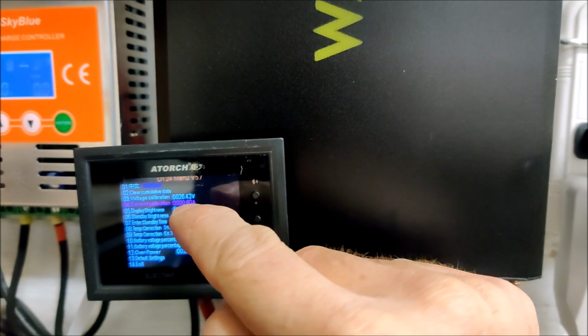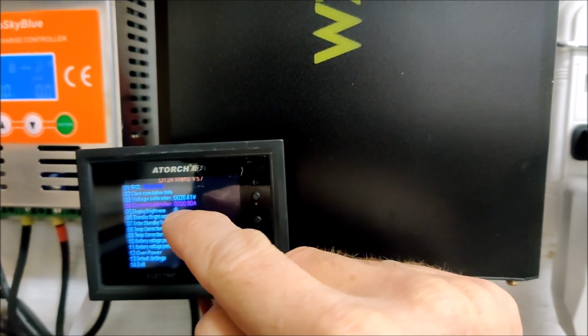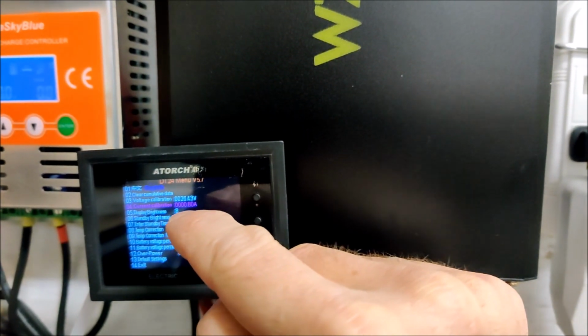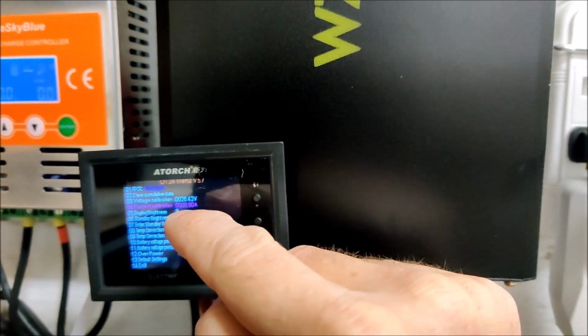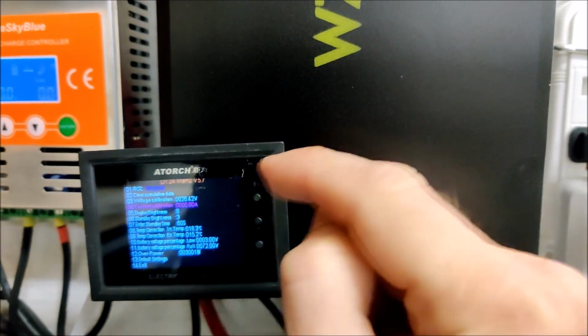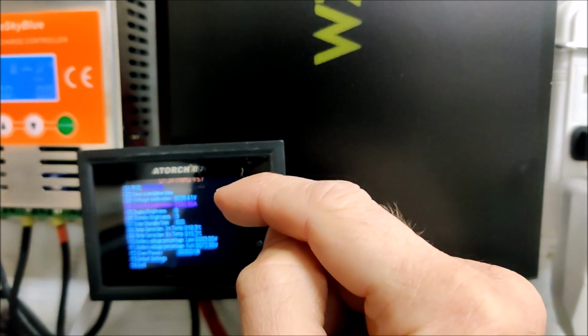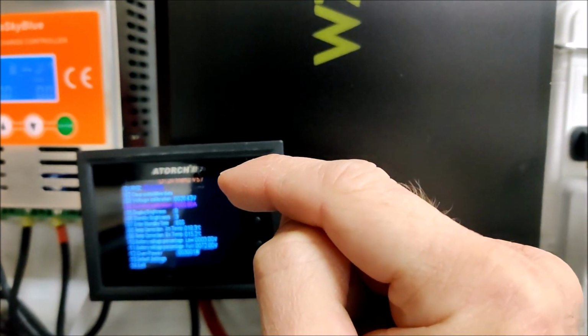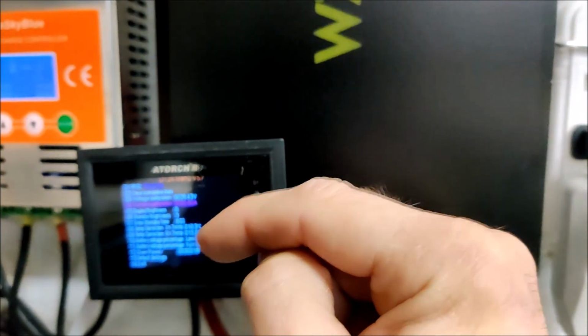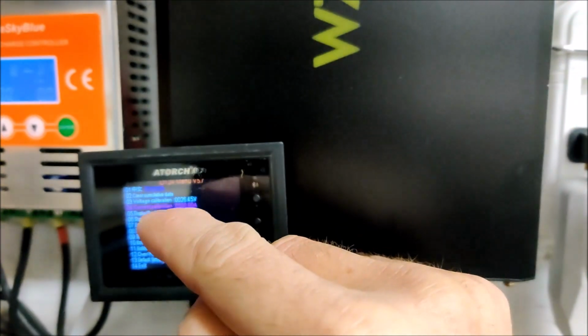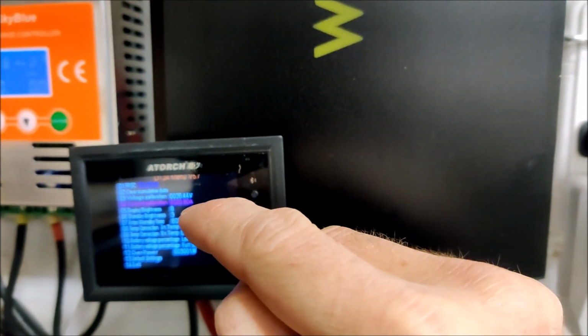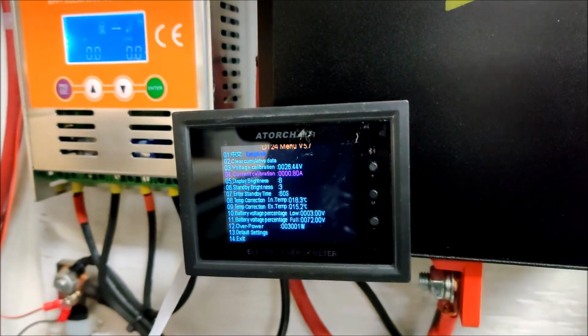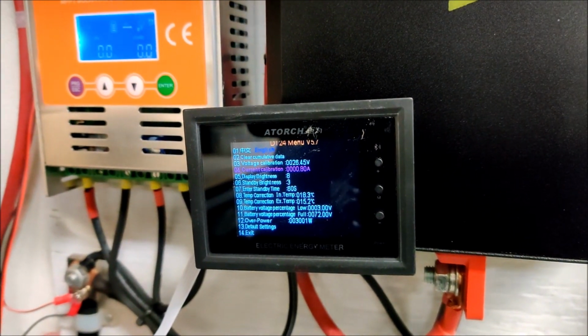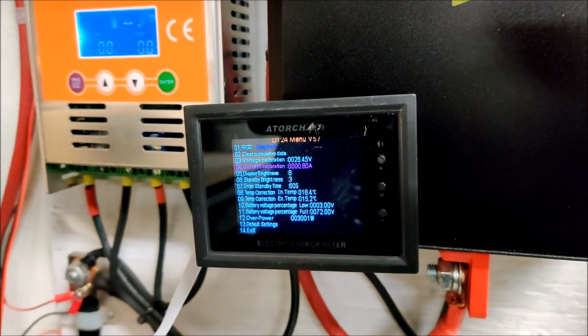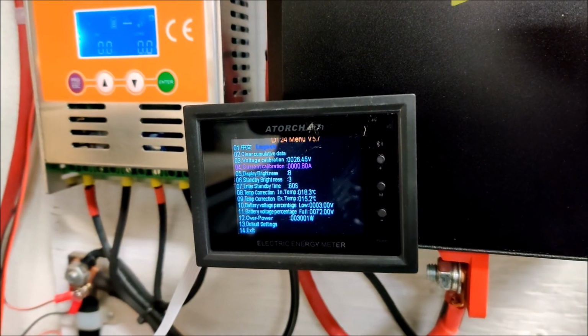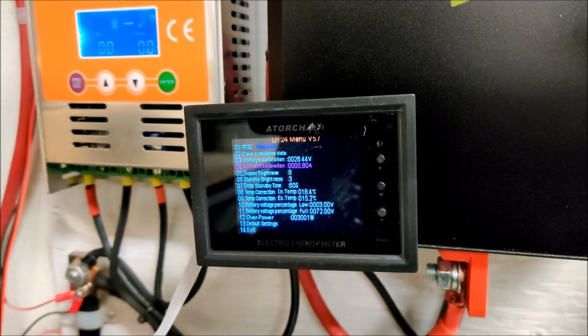So yes, I could definitely dial this in to 35 amps at the 35 amp pull, but then it will be monstrously off at 10 amps or 60 amps. Putting in an offset here has proved kind of useless, because that offset is only accurate at the current draw that you're programming the offset in.